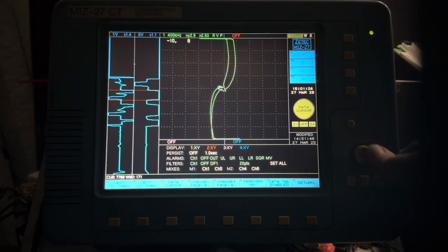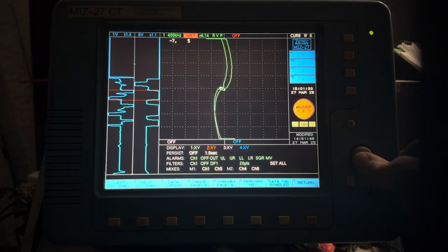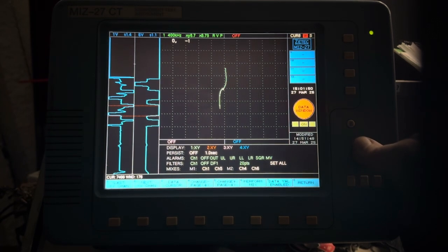So what we'll do is I'm going to bring the span down even more. So this is going to be the largest of the 3. Okay, so I get that one totally on the screen. And now when I go down to the other two, that's the medium one, medium depth. Make my window a little bit bigger here so you can see it. And that's going to be our smallest wear scar. So you can see how the volume of metal missing contributes towards the voltage or the size or the amplitude of that signal, whatever you want to refer to it as.